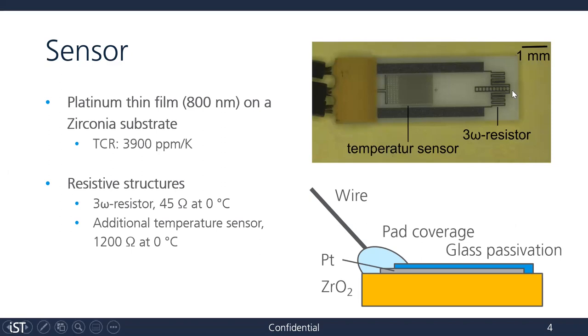The pattern structure contains two structures. One is the heater or the three omega resistor used to perform the three omega method, with a value of 45 ohms at zero degrees. There is also a second structure with a value of 1200 ohms at zero degrees. The idea of this second structure is to measure the ambient temperature of the fluid.